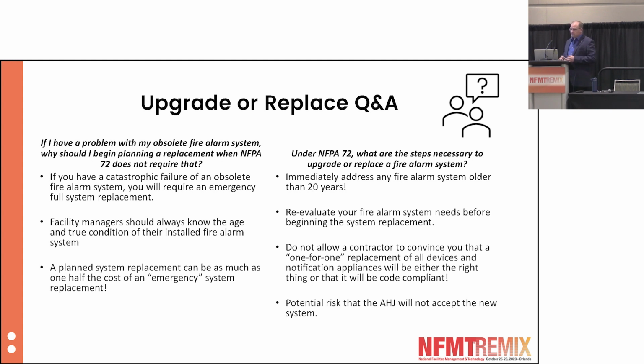Now, under NFPA 72, what are the steps necessary to upgrade or replace a fire alarm system? Well, NFPA 72, again, as an installation standard, doesn't specifically address this issue, but you need to be making plans immediately to address any fire alarm system that's over 20 years old, especially if it's nearing that 25-year limit. You want to reevaluate your system's needs to see what you might need for any new system going in the future. Never allow a contractor to convince you that a one-for-one replacement of all devices and notification appliances will either be the right thing to do or that it will be code compliant.